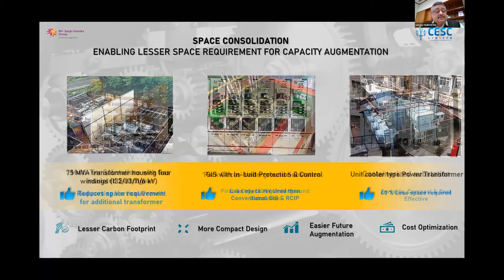Now some more such things - we have transformers with four windings: 132 by 33 by 11 and 6. Since we are a legacy organization, we have both 6 kV and 11 kV networks in Calcutta. I don't think any other discom in the country has both 11 kV and 6 kV, and we are still maintaining both voltage levels. So we've developed, with OEMs, transformers having these four windings, since it takes very little space.